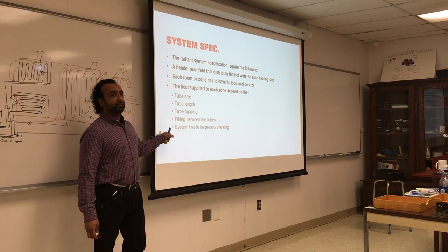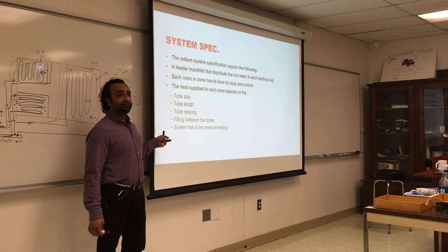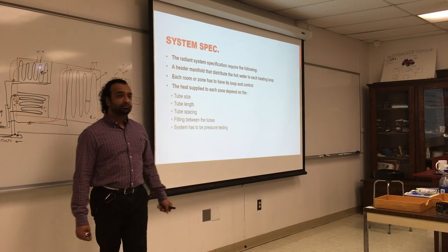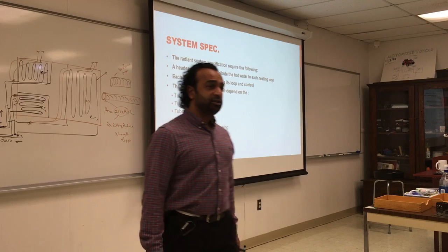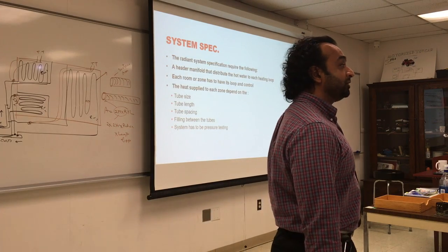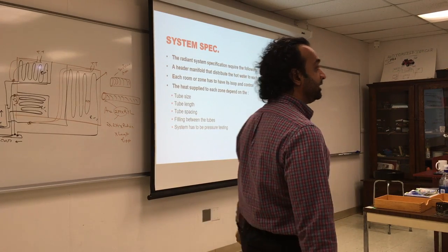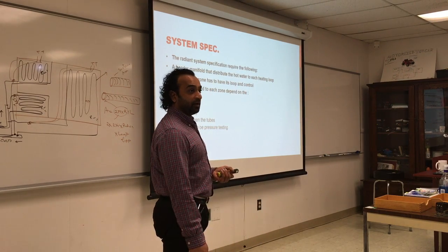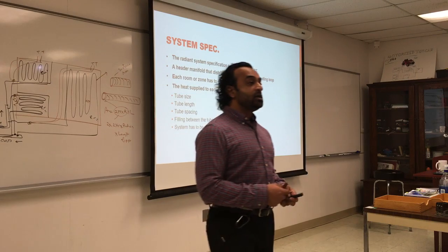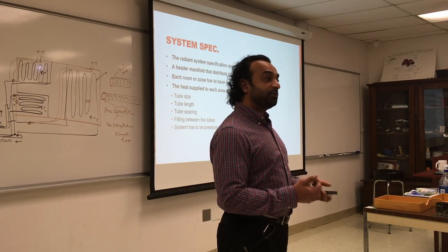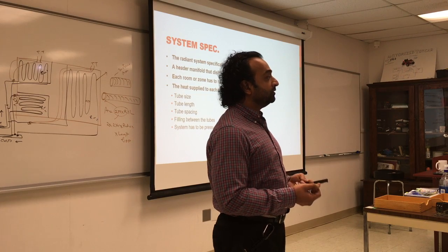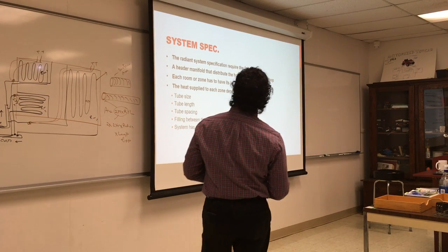You don't pressure test it and wait. You pressurize it and leave it overnight to see if there's any drops in the pressure. Sometimes a small drop you cannot detect or see visually, so you monitor the leaks by performing elaborate system pressure testing over a period of time. You pressurize it, you leave it, and you see if the pressure drops. If the pressure drops, it means there's some leak in the system, and you have to go and review all the soldering and connections.